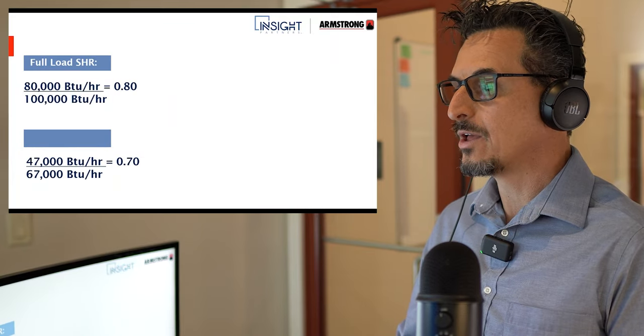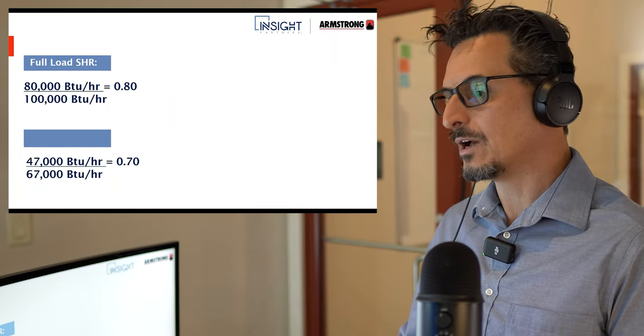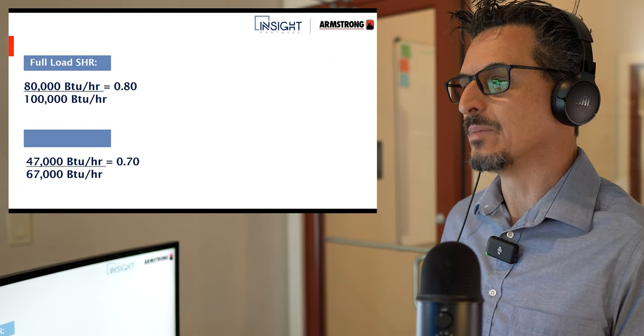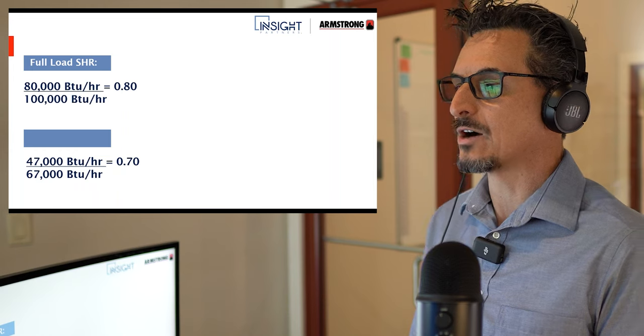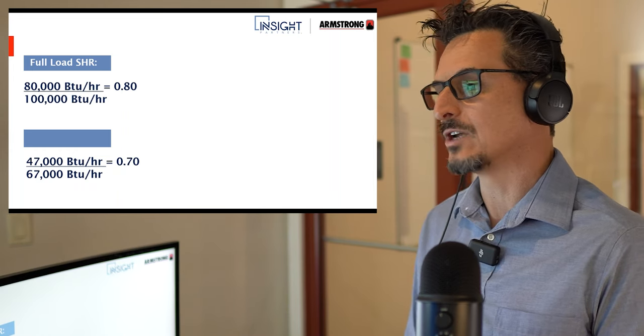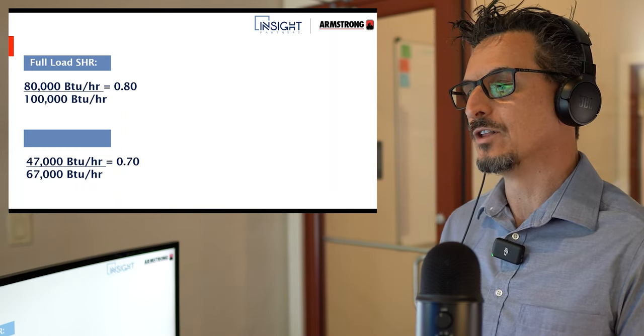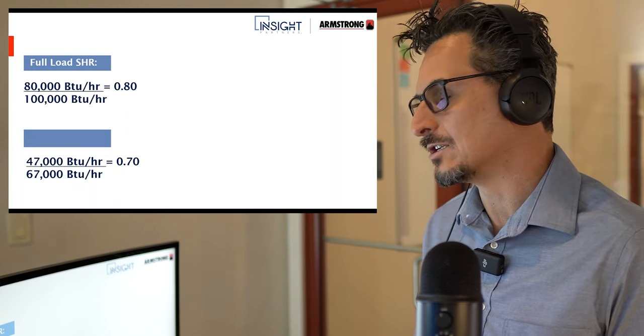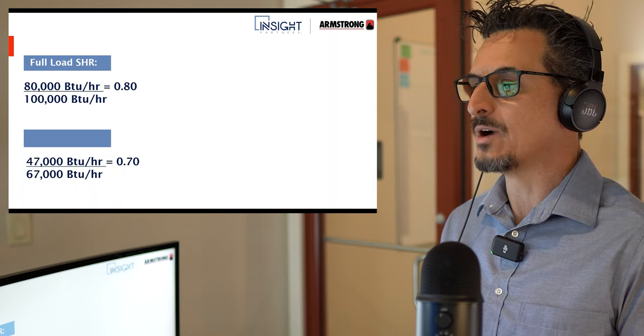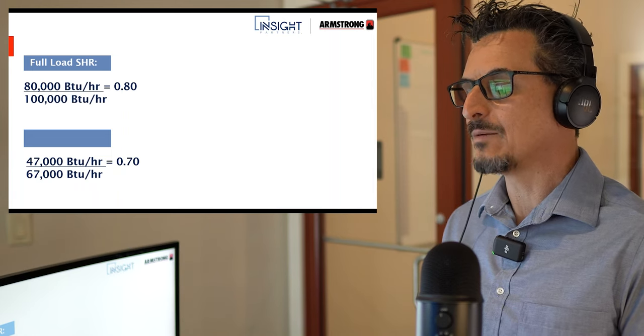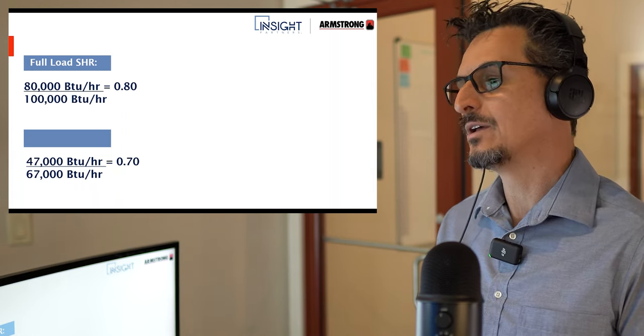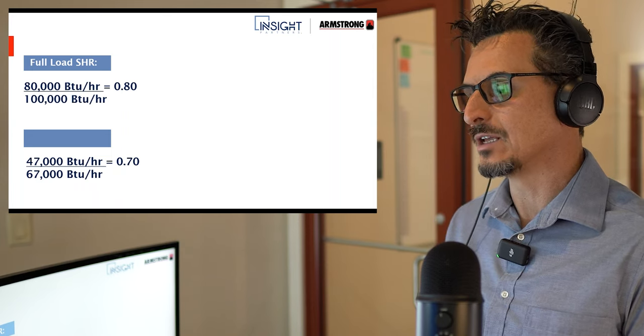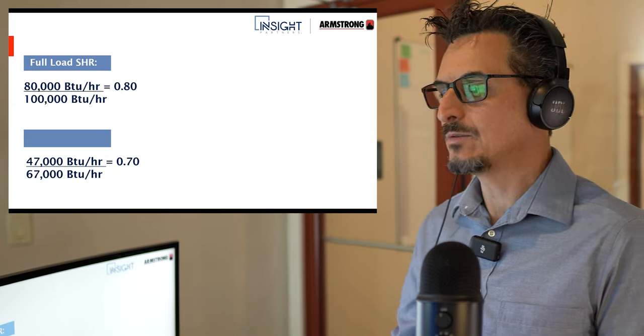So we're going to look at these two conditions here. That should say part load on the bottom. So the full load SHR — these are the examples we used in the psychrometrics presentation. The full load SHR is 80,000 over 100,000, which is a 0.8. We're going to design for that, and then see what happens at part load.